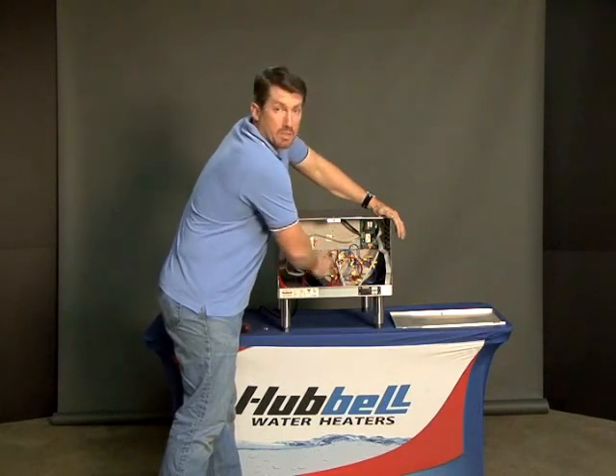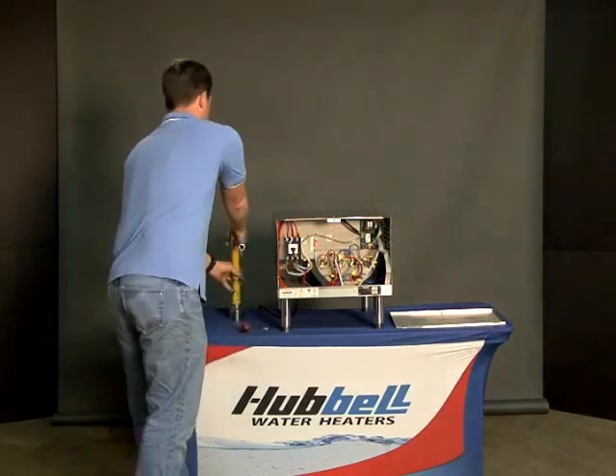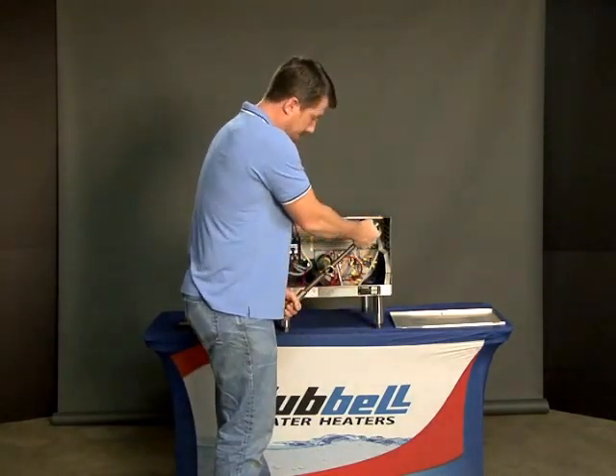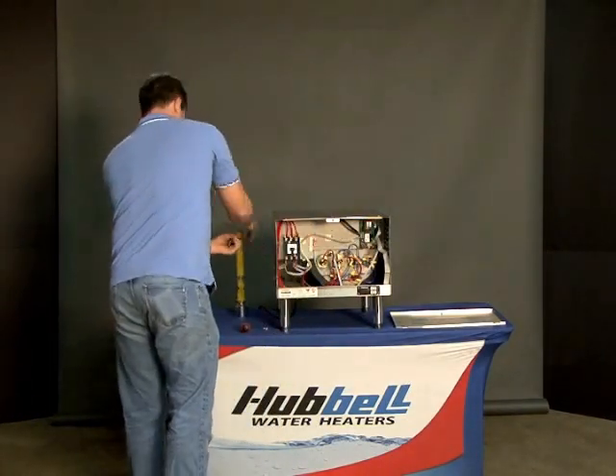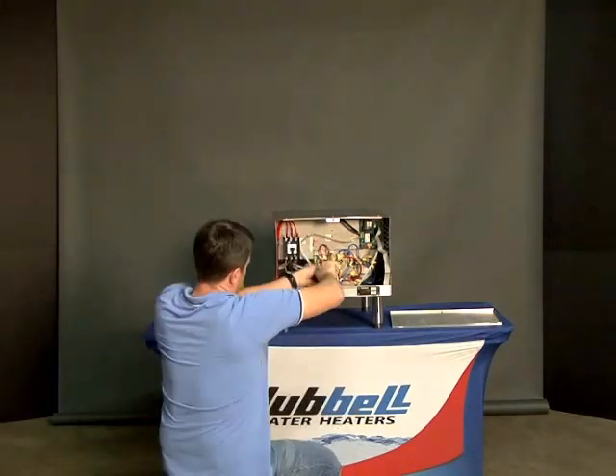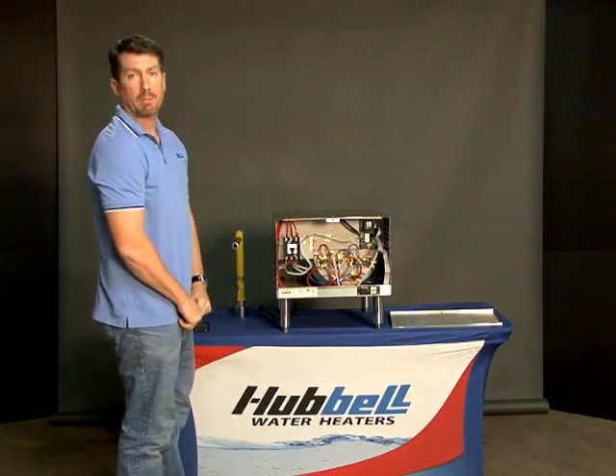Remember, this is a straight thread, so you'll be able to turn it most of the way by hand. Once it tightens up, use your standard inch and seven-eighths socket and just give it that last little snug at the end. Then replace the wires onto the element. And there you have it — the installation of a heating element in the Hubbell J Model Booster.